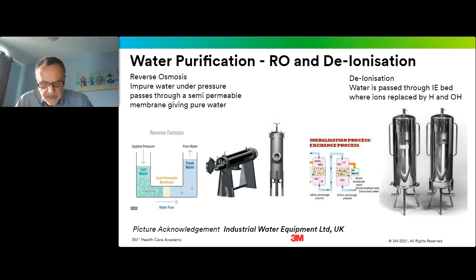But one of the problems with deionization is that the systems require regular regeneration using acid and alkali washes to remove the cations and anions and restore the resins back to their starting point. So at some point in the day or the work period, a regeneration process may be needed. In some cases, many people will just use ion exchange resin pods, which they swap out on a regular basis with a supplier or manufacturer. Now, distillation, of course, is also possible, but it's very rarely found in a sterile processing department. It's typically used in the pharmaceutical sector for producing ultra-pure water, and single and double distillation may be used to make sure the water is very, very pure.